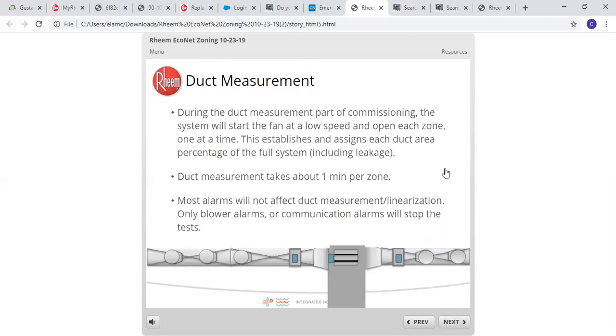This gets into the duct measurement. During the duct measurement part of the commissioning, the system will start the fan at low speed and open each zone one at a time. This will establish and assign each duct area a percentage of the full system, including leakage. Duct measurement takes about 1 minute per zone. Most alarms will not affect duct measurement or linearization. Only blower alarms or communication alarms will stop the tests.